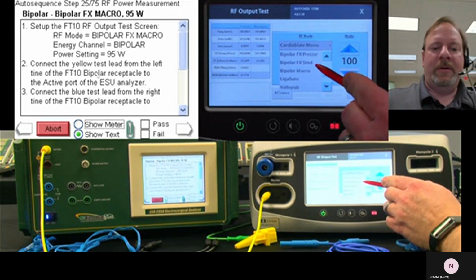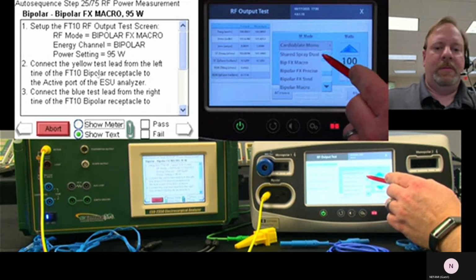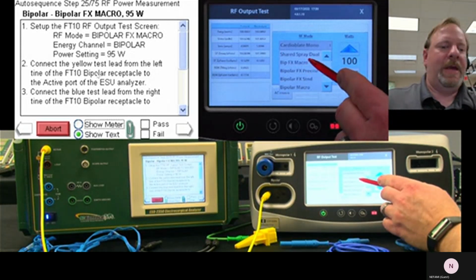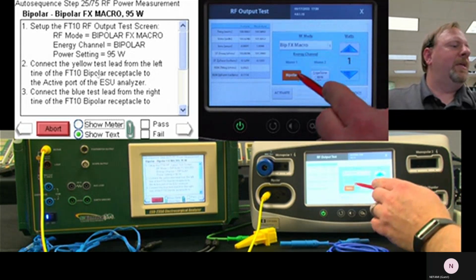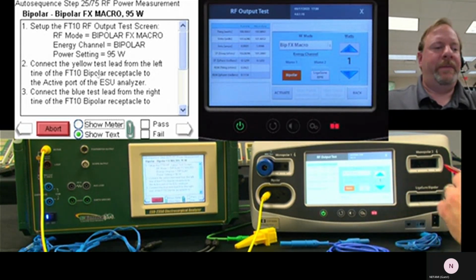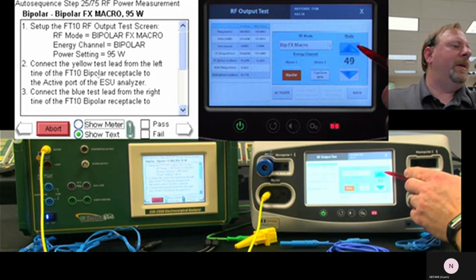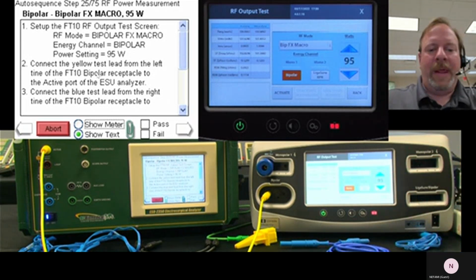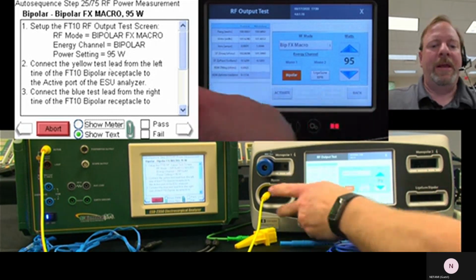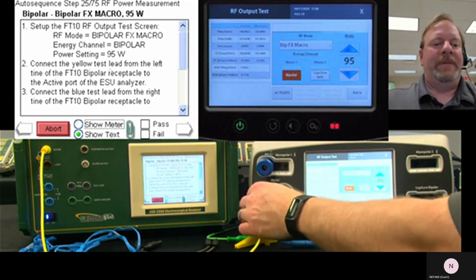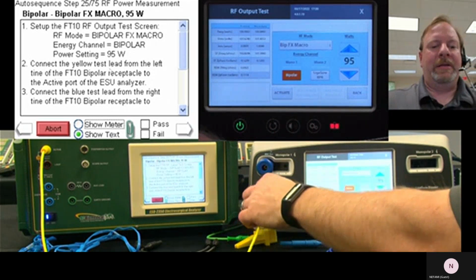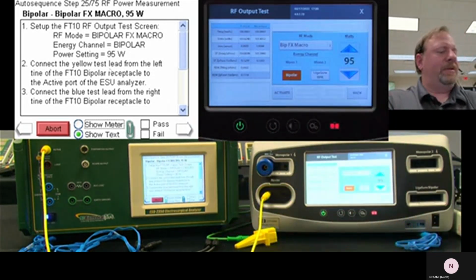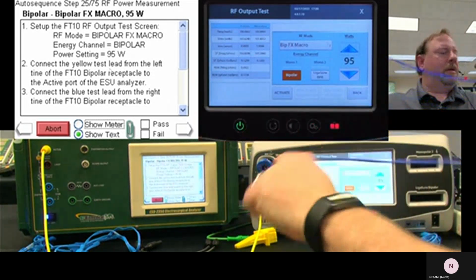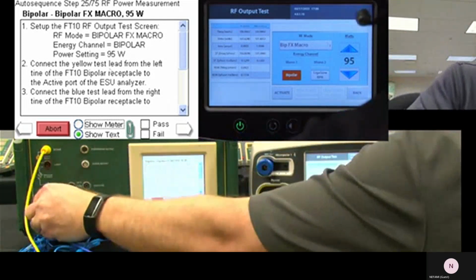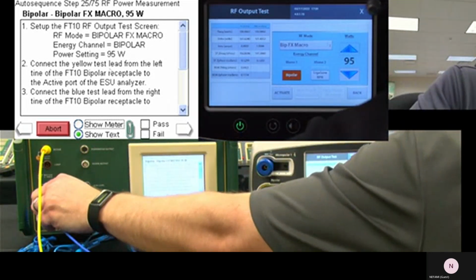Okay, so now we're going to do bipolar, and I'm going to see if I can find it. Bipolar macro, FX macro, nonetheless. On the bipolar port, it automatically found that for me. And so again, now we have to change things because we're testing bipolar. Connect the yellow from the left side of the bipolar. We're on the left side. And then we have a blue test lead, and you can go to either dispersive port, doesn't matter.